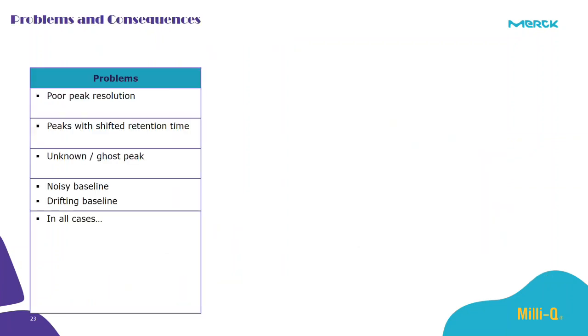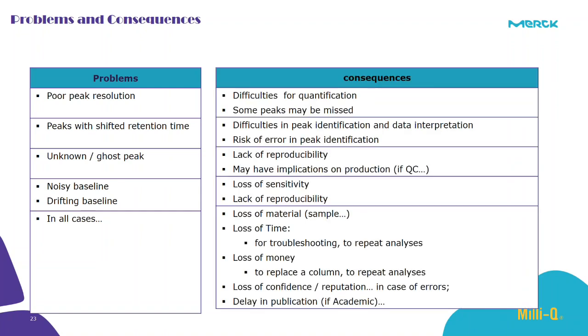So some problems and the consequences. The first problem is that you may face poor peak resolution. The consequences will be difficulties for quantification, and some peaks may be missed. Second, the problem is peaks with shifted retention time. The consequences may be difficulties in peak identification and data interpretation, and risk of error in peak identification. Third, the problem is unknown or ghost peaks, and the consequences may be lack of reproducibility, and may have implications on the production. Some problems are also noisy baselines and drifting baselines.